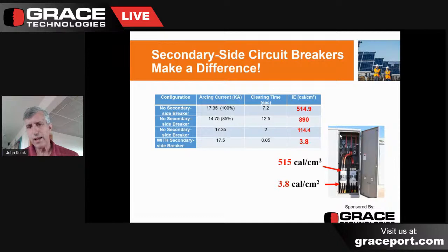And of course, when you're talking about 890 calories, it probably wouldn't last 12 seconds, as you can see. It would probably melt in the clear before that time. But from a calculation standpoint, it would be considerably higher. Now, if you use the recommendations in the 1584 regulations, they would suggest that we clear all faults in 2 seconds or less. If that were true, it would calculate to only 114 calories of incident energy. Well, of course, that's very significant.